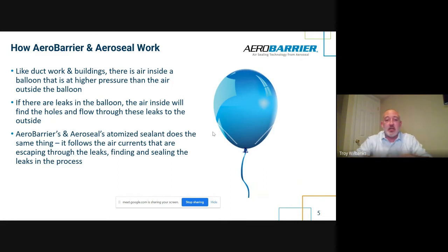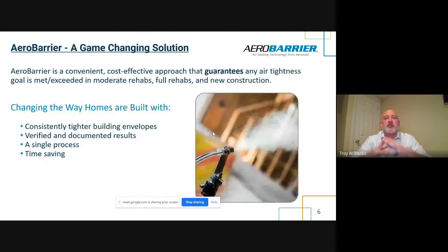That's the same working principle that both Aerobarrier and Aeroseal technology operate on: positive pressure on the inside of ductwork or a home, unit, condo, apartment, warehouse, whatever that may be. We're going to put positive pressure in, and it's going to force air out to the leak points and carry sealant with it, sealing it up in the process. So that's just a high level overview framework of how it works.